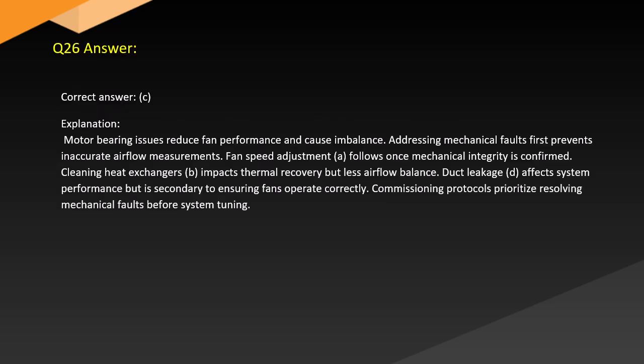Answer. Correct answer: C. Explanation. Motor bearing issues reduce fan performance and cause imbalance. Addressing mechanical faults first prevents inaccurate airflow measurements. Fan speed adjustment (A) follows once mechanical integrity is confirmed. Cleaning heat exchangers (B) impacts thermal recovery but less airflow balance. Duct leakage (D) affects system performance but is secondary to ensuring fans operate correctly. Commissioning protocols prioritize resolving mechanical faults before system tuning.